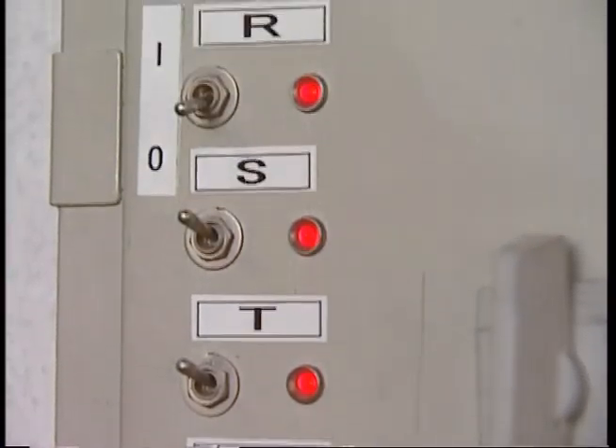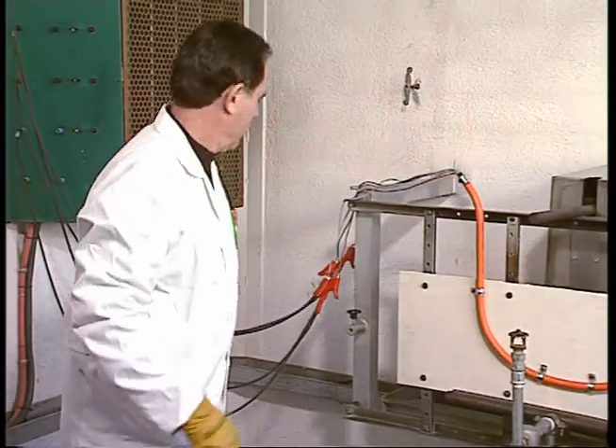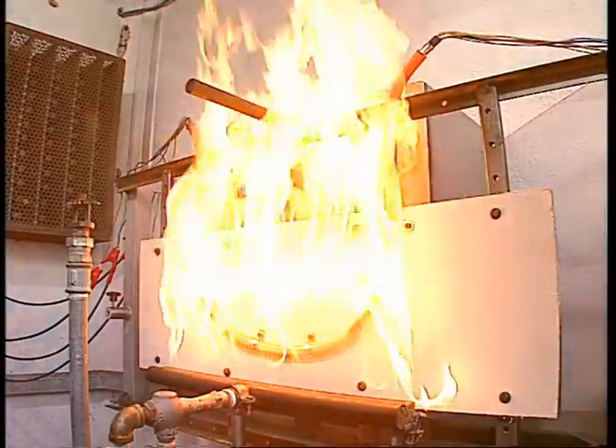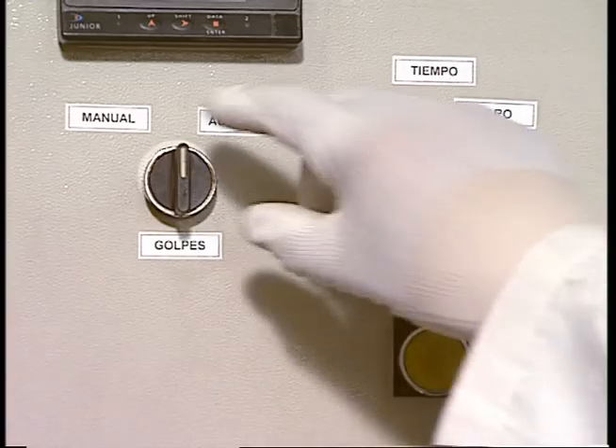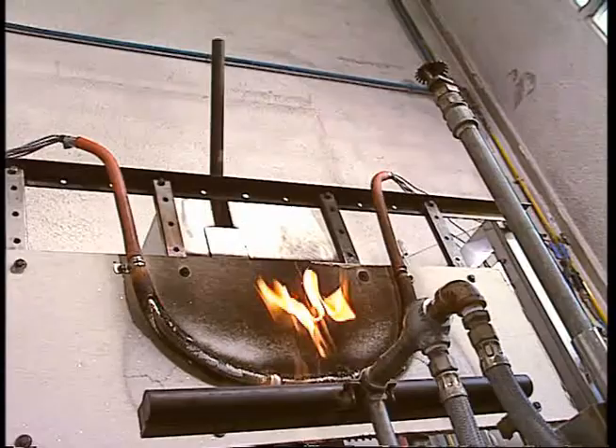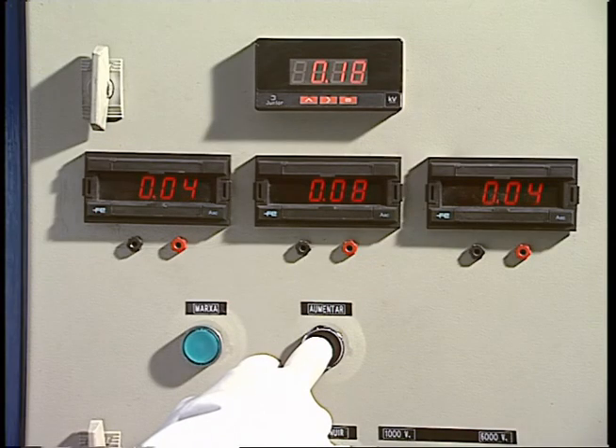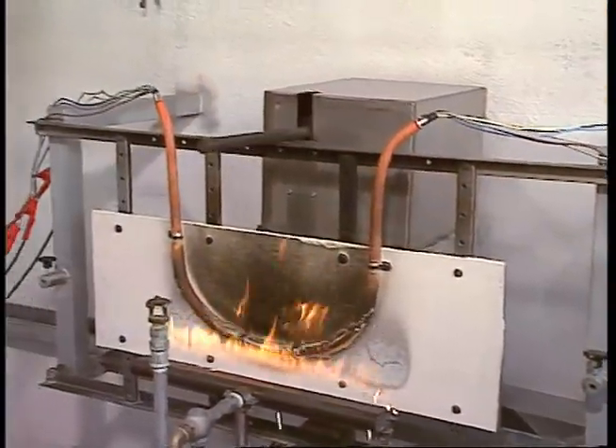The system is equipped with a circuit for checking the continuity of the cable and a control panel which shows us the time elapsed. After connecting the cable's leads, we apply the fire from a burner to the cable, starting the countdown, and activate a motorized metal bar which strikes the system every 5 minutes. We apply a test voltage of 1 kilovolt and check that the continuity of the circuit is maintained while the cable is burning and being struck.